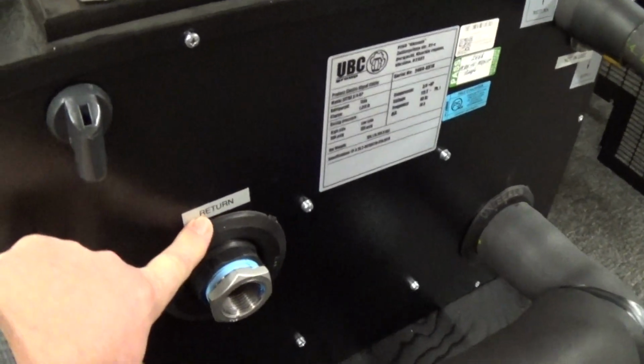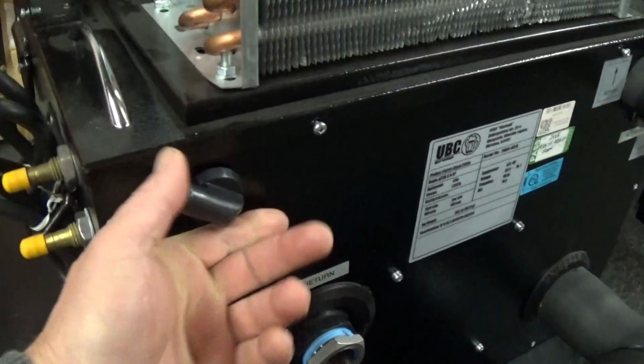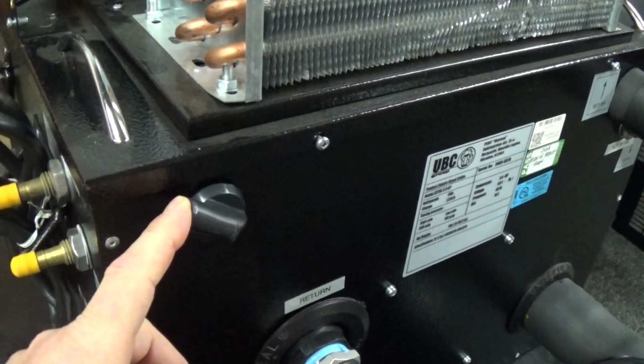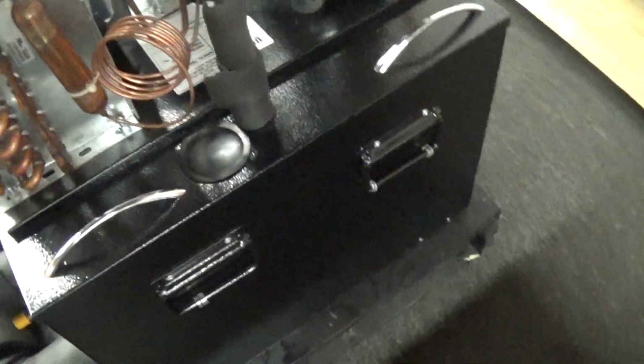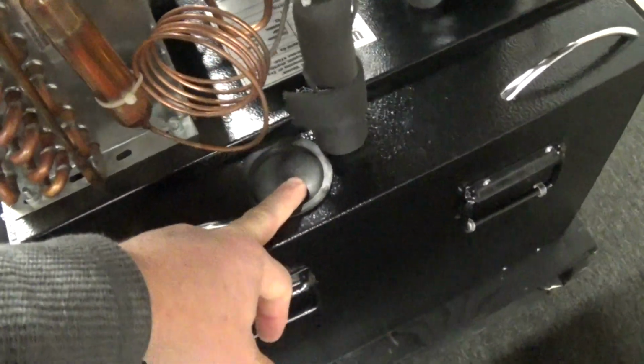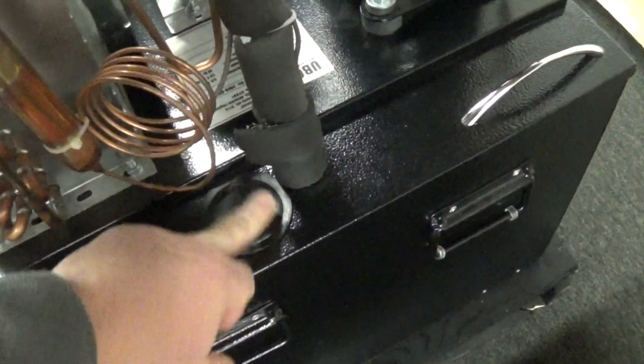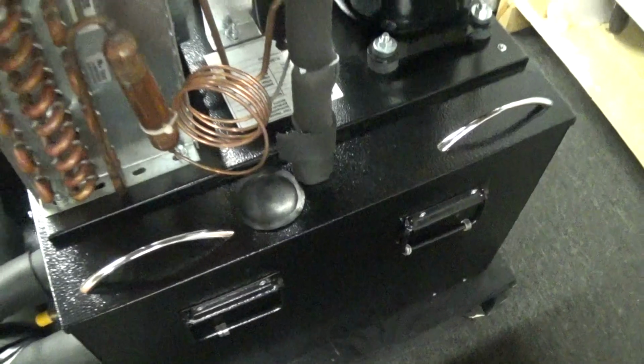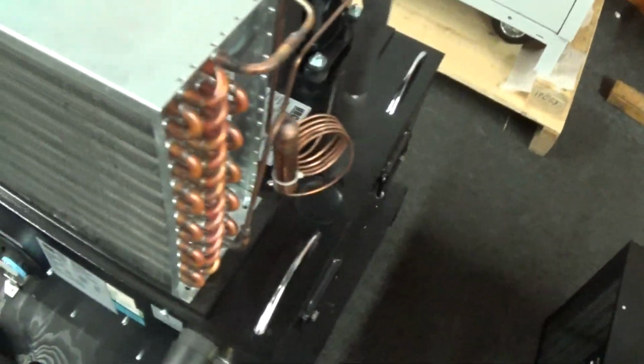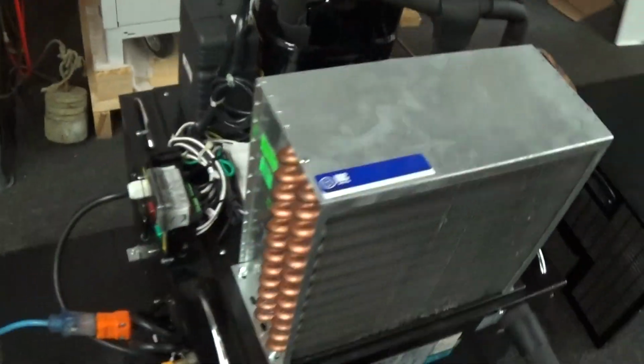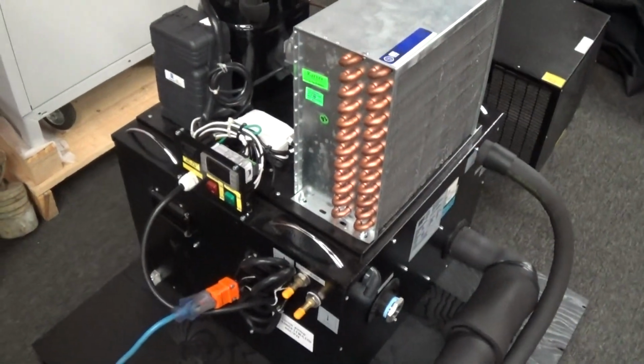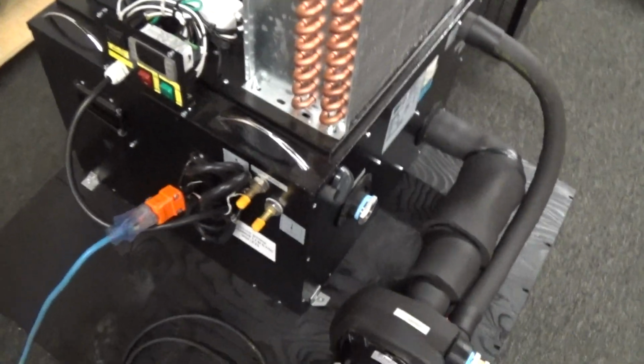This is your return here. This is a vent for your glycol. To put glycol in the system, again, we have the cover off. You can take this little 2-inch diameter plastic lid off to get your glycol concentration in there. 40 or 45% propylene glycol is ideal.